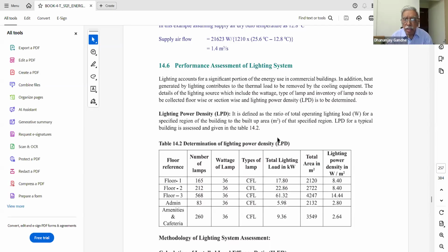Now, total lighting load will consist of the wattage of lamps in various areas. But usually there is a practice that they define what is called the lighting power density. So what is lighting power density? That was also described when we studied illumination, but again, I will repeat: lighting power density is the ratio of total operating lighting load in watts, not kilowatts, to the built-up area. The total operating load, that is the working load, may be different from the installed load, because many lamps may be installed but not in operation. So what we need to consider is the total operating load, the functional load of lighting in watts, divided by the built-up area. That is the lighting power density.